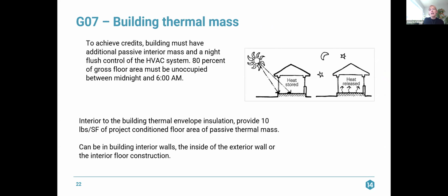Building thermal mass. So the idea here is that a building has thermal mass that is open to the ambient air inside the building to absorb heat and reject heat. So the building must have interior mass, and it can be a part of your structure as long as it is either just covered by gyp, or it can be, you have an interior wall of a gymnasium, something like that, that is mass, right? Because you have kids that are going to run into it, throw kickballs at it and stuff. You can't have a steel framed wall.